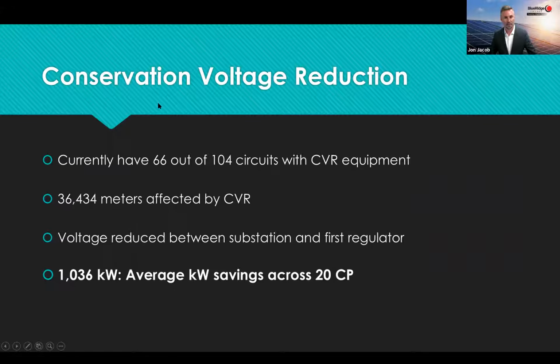So quickly, conservation voltage reduction, again, is Don Bowman's baby, but we do it on about two-thirds of our circuits. 66 of the 104 circuits we have are equipped with CVR equipment. There's a total of about 36,000 meters affected by conservation voltage reduction. We reduce voltage between the substation and the first regulator on these circuits, and last year it provided just over 1 megawatt of demand savings across all our 20 CP hours. That was the average.